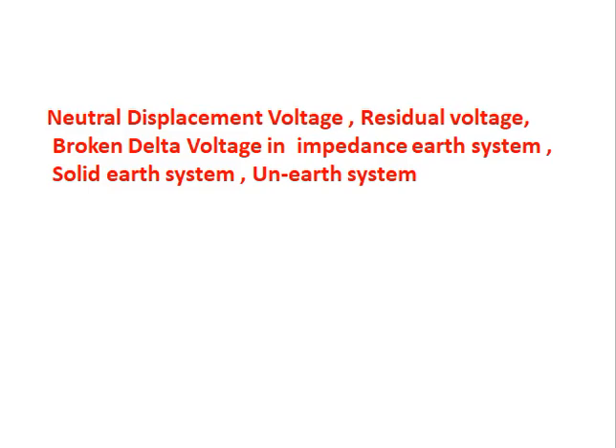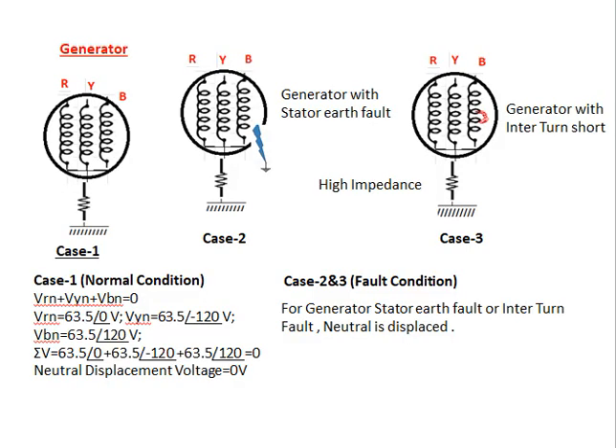Generally, one side of the generator stator windings is connected as a star and connected to earth via high impedance — this is called high impedance earthing. The other side connects to the load. In normal conditions (Case 1): Vrn + Vyn + Vbn = 0, where Vrn = 63.5∠0°V, Vyn = 63.5∠−120°V, Vbn = 63.5∠120°V. The summation of these voltages equals zero, so neutral displacement voltage equals zero.